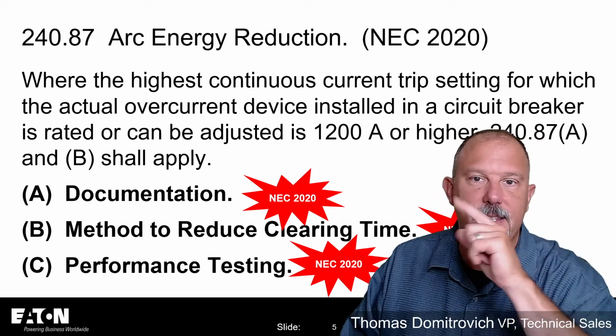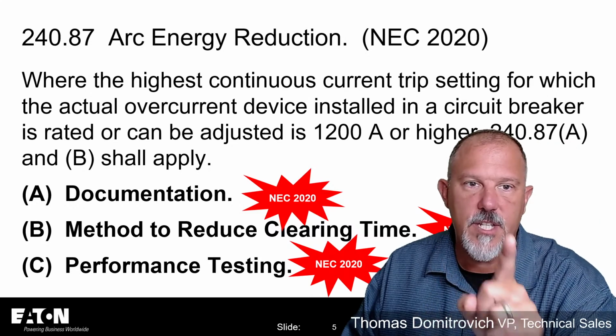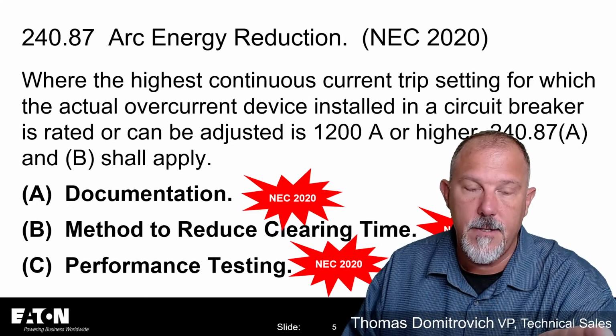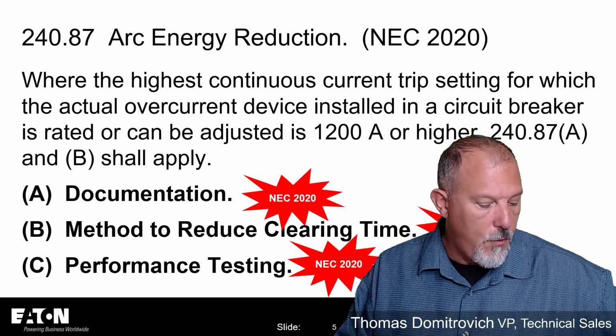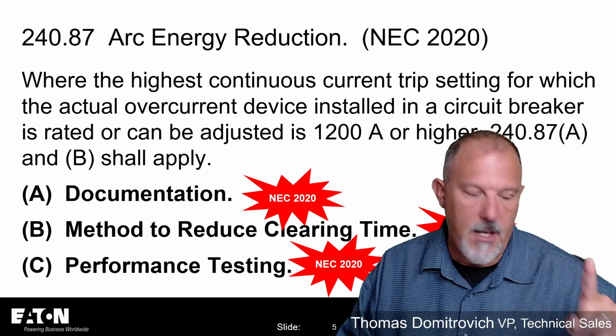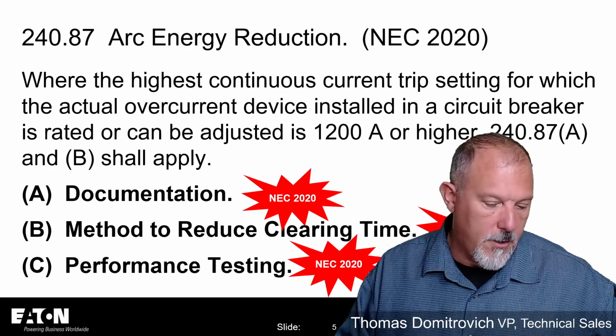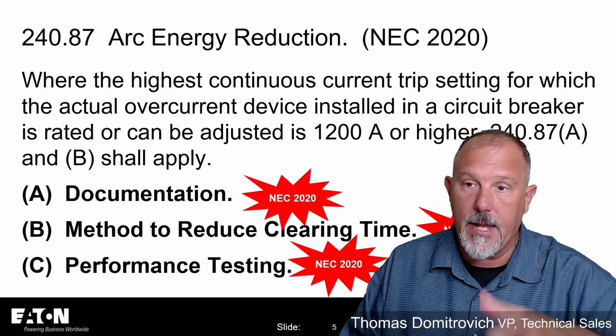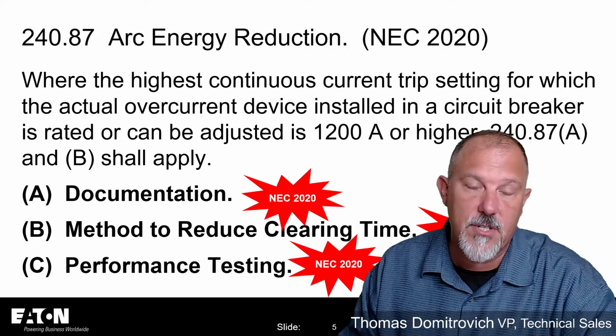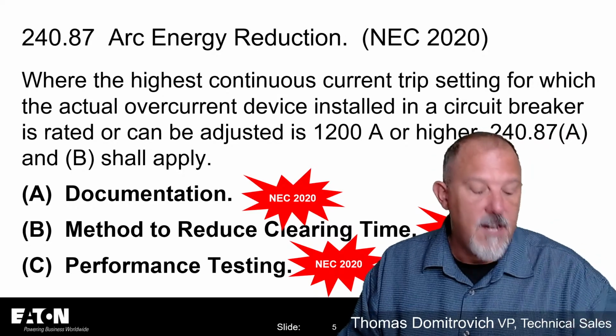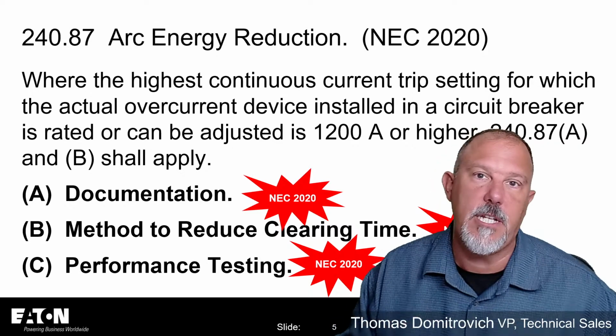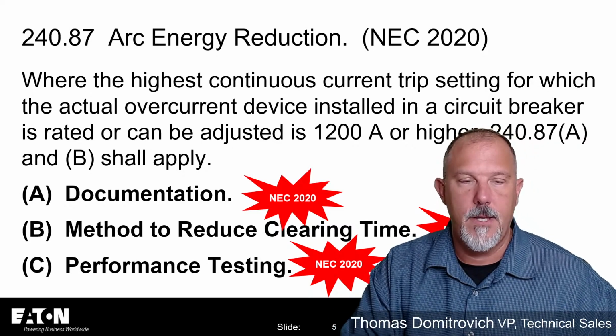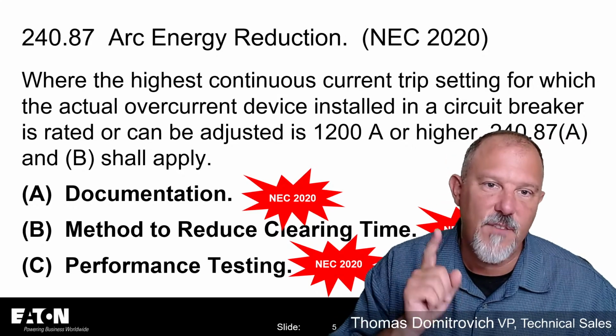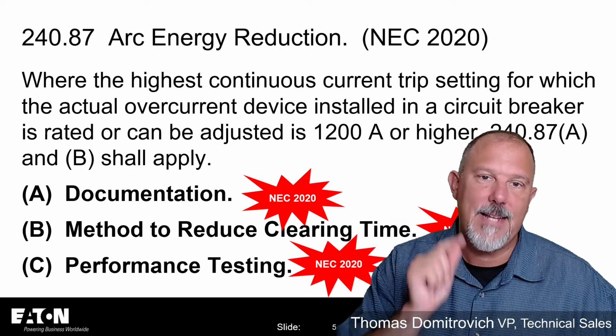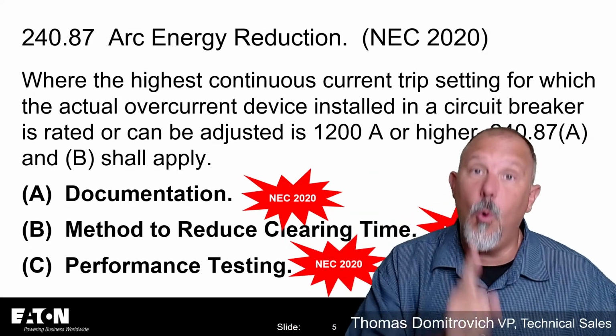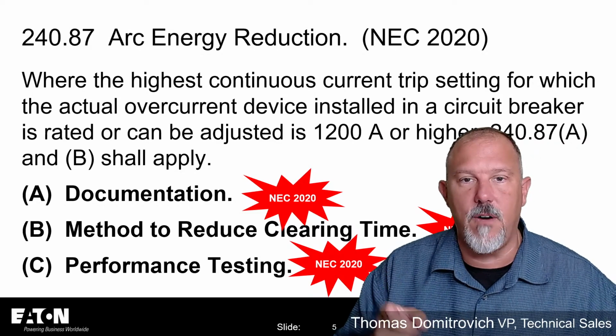240.6, remember, this says where the highest continuous current trip setting for which the actual overcurrent device installed in a circuit breaker is rated. And where do we go to get the rating? We go to 240.6. Don't make this mistake and think that because I have an adjustable trip circuit breaker and I adjust it to 1,000 amps, and it's a 1,200 amp frame breaker adjusted down to 1,000 amps, and I have a door, that the rating of that breaker is now 1,000 amps, and I don't need to do 240.87. And the reason you can't do that is because of the next few words in this paragraph. It says, in a circuit breaker is rated or can be adjusted is 1,200 amps or higher.